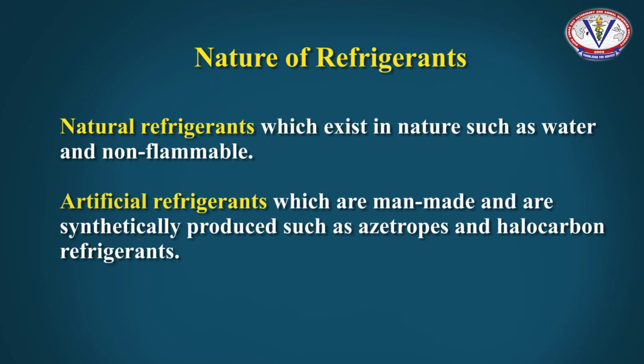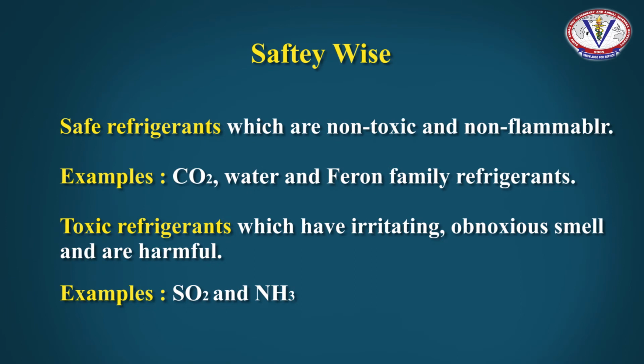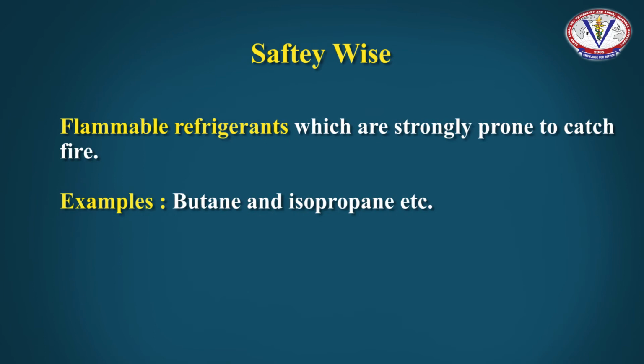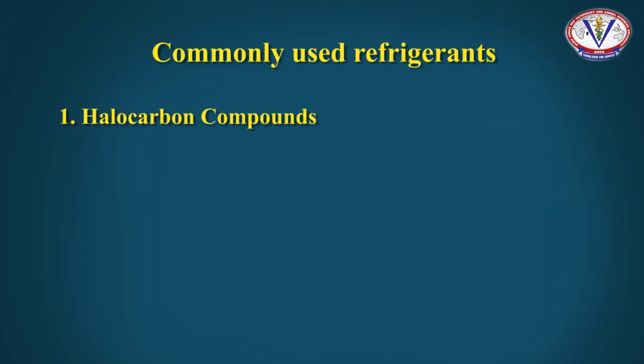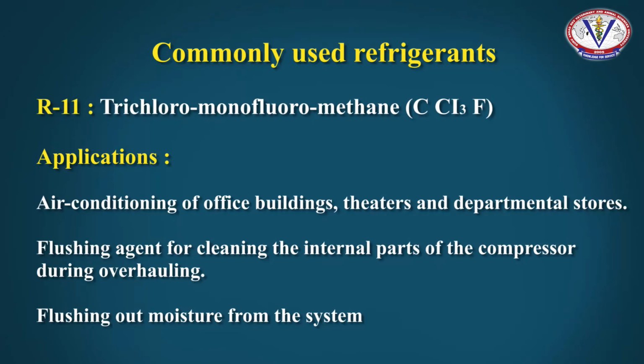On the basis of nature, refrigerants can be natural refrigerants which exist in nature such as water, and artificial refrigerants which are man-made and synthetically produced such as azeotropes and halocarbon refrigerants. Safety wise, safe refrigerants are non-toxic and non-flammable, for example carbon dioxide, water and freon family refrigerants. Toxic refrigerants have an irritating or obnoxious smell and are harmful. They include sulfur dioxide and ammonia. Flammable refrigerants, which are strongly prone to catch fire, are butane and isopropane, etc.